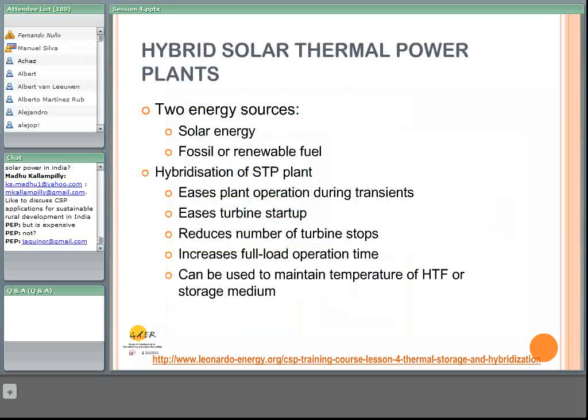Hybridization consists basically in using two energy sources, solar energy and fossil or renewable fuel. Of course, if we have these two energy sources, we can take advantage of the fuel to operate during transients, or to start up and warm up the turbine before the sun rises, to reduce the number of turbine stops, or to increase the full load operation time. Hybridization can even be used to maintain the temperature of the heat transfer fluid or the storage medium.